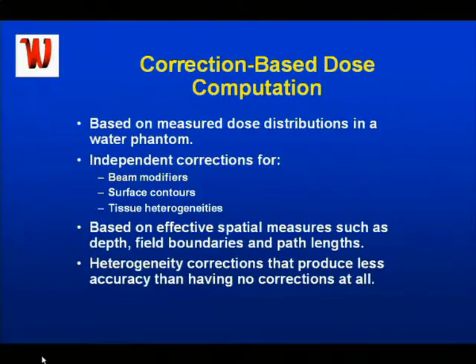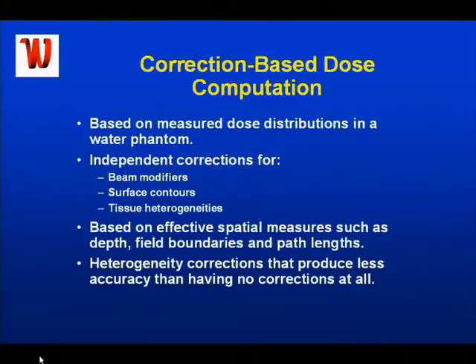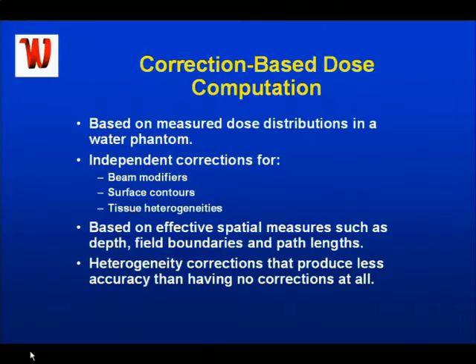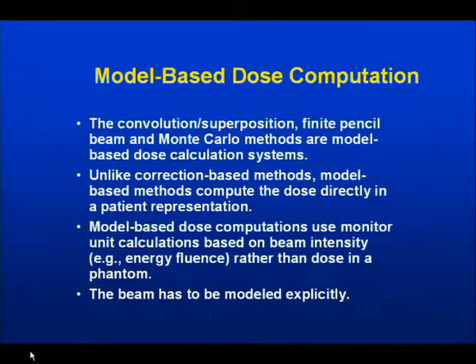We're really talking about types of calculations that you have to use a computer for — these aren't hand calculations. The correction-based dose calculation models that existed really up until the mid-90s were essentially based on calculations that evolved from hand calculations. So they're really based on measured dose distributions in a water phantom. You then had independent corrections for the beam modifiers — for example, wedges and compensators — for surface contours, and for tissues within the body. They're really based on effective spatial measures such as the depth in the field, the field boundary, and path lengths.